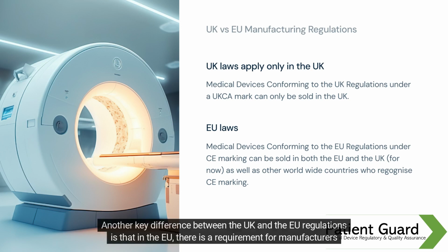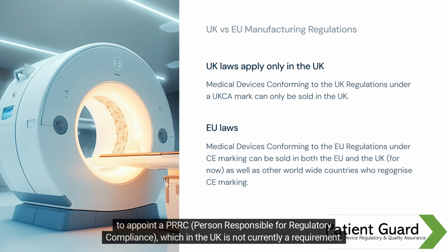Another key difference between the UK and the EU regulations is that in the EU, there is a requirement for manufacturers to appoint a PRRC, person responsible for regulatory compliance, which in the UK is not currently a requirement.